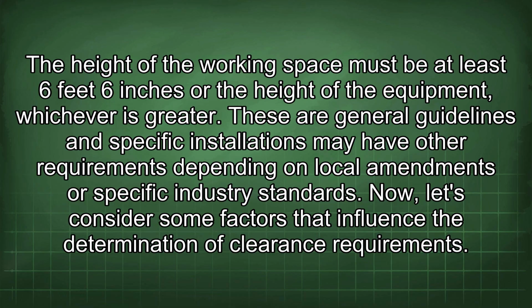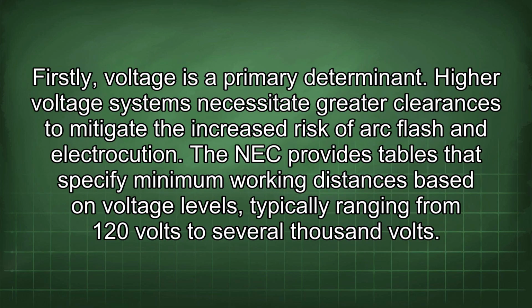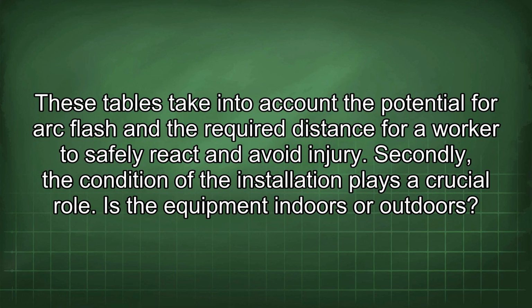Now let's consider some factors that influence the determination of clearance requirements. Firstly, voltage is a primary determinant. Higher voltage systems necessitate greater clearances to mitigate the increased risk of arc flash and electrocution. The NEC provides tables that specify minimum working distances based on voltage levels, typically ranging from 120 volts to several thousand volts. These tables take into account the potential for arc flash and the required distance for a worker to safely react and avoid injury.